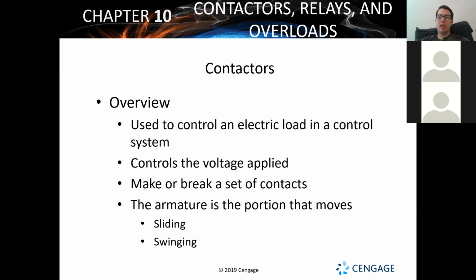That's the only two types of contactors you're going to have. They're either used to connect power or disconnect power. And understanding how to read that voltage is important. So you're going to have one lead as your power coming into your contactor, and the other lead is going to be your power coming out, going to your load typically. So going to your compressor, going to your condenser fan motor, going to your blower motor, whatever it might be. The difference of voltage between those two sides can be determined just by putting the leads pretty much on the bottom and top of the contactor on the same side.